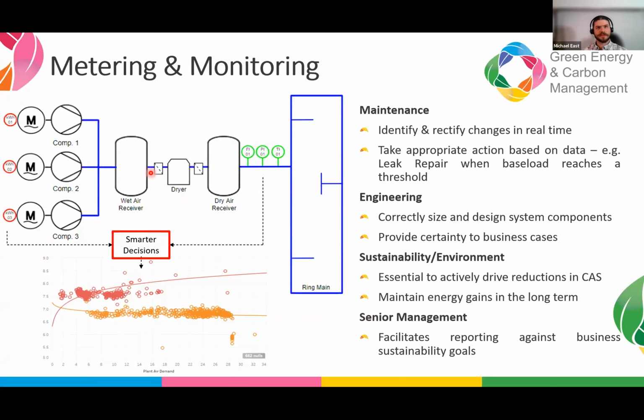But something I think is overlooked with metering systems and applications to compressed air is what value that actually adds to each layer of a business. If you've got metering in place, your maintenance teams can start to question: okay, service techs came in last week and did a service of the machines - did they change set points? So we're still operating our control logic and maintaining our efficiency. That metering gives you transparency over that. It also lets maintenance teams keep track of the leak loss rate on the site, and whether it's actually worthwhile going around chasing and fixing those leaks.